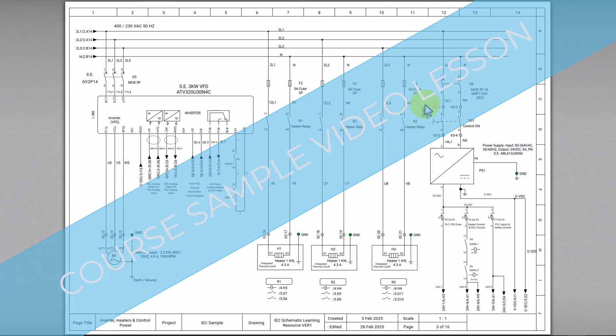Okay. And then over on the right, we have a DC power supply that is tapped off of the same bus and the neutral. And that is for our control power.